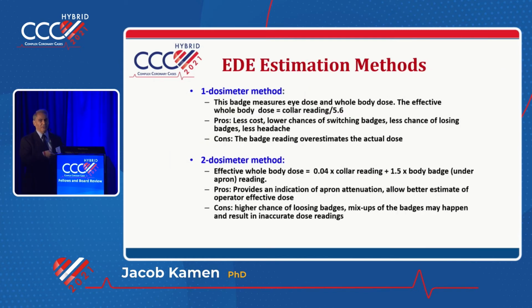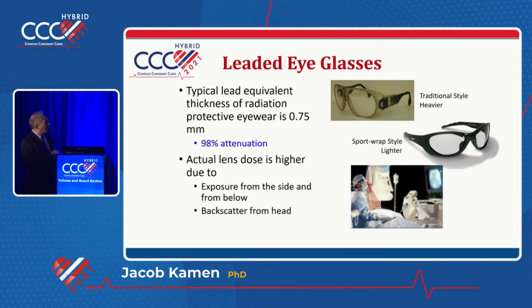There are benefits and disadvantages of having one badge compared to 2 badges. I'm not going to go over that because we have a lot to cover. Lead eyeglasses are very important. There is less than 1 millimeter of lead in them, but it reduces exposure by 98%. So lead eyeglasses are crucial for you.